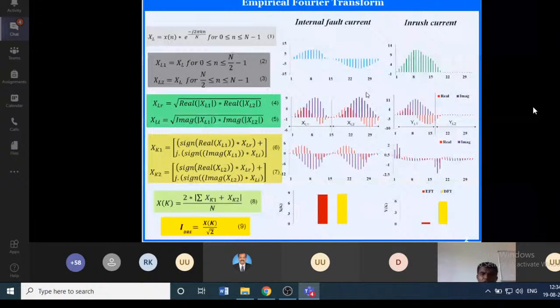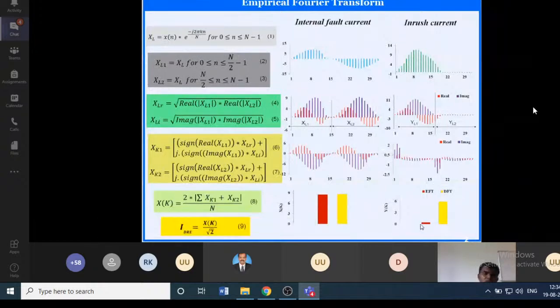When you multiply both positive and negative, you will have a significant amplitude equal to the Fourier transform. The brown color is the EFT, that is, the empirical Fourier transform result. The yellow color represents the DFT. In case of internal fault current, the magnitude estimated using the EFT is almost equal to the DFT. In case of inrush current, the EFT gives a very small component. So it gives a clear picture between the internal fault current and inrush current. This is the advantage of the empirical Fourier transform, and we can understand how to use this signal processing tool for electrical engineering.